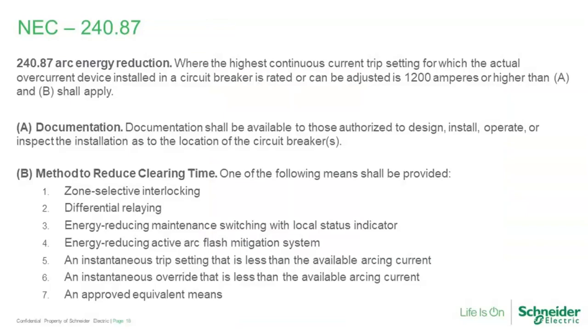I mentioned the National Electrical Code. One of the things that has changed in recent years, and is still rolling out as different states and local authorities adopt new editions of the code at different rates, is the requirements for arc energy reduction. This one talks about NEC 240.87. There is a similar article, NEC 240.67, that deals with fuses, but I'm just showing you one to give you the idea. This text is based on the 2017 National Electrical Code. The 2020 is essentially the same. There's a little bit of a change, but it still hasn't been adopted in most states yet, so I think 2017 is still fair to look at.